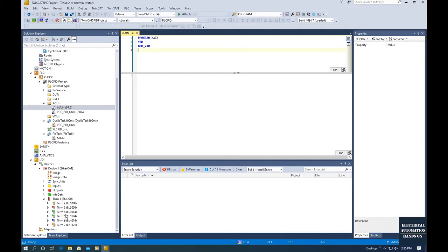To use the analog card, we need to check the manual and figure out two things. First, how to wire the current or voltage analog input channel. Second, what the full range of this channel is — meaning after the signal is connected to the analog channel, the internal ADC transfers the analog signal to a digital value, and there is a full range for that digital value. For Beckhoff analog cards, the full range is mostly 32767. For Siemens analog cards, the full range is 27648.